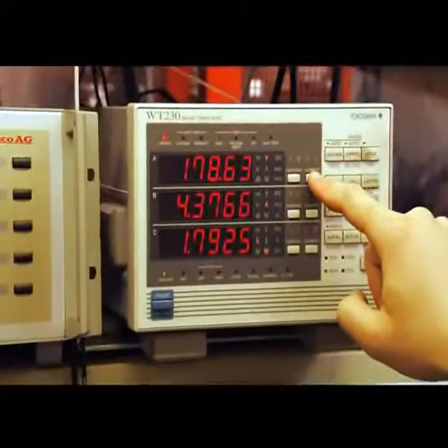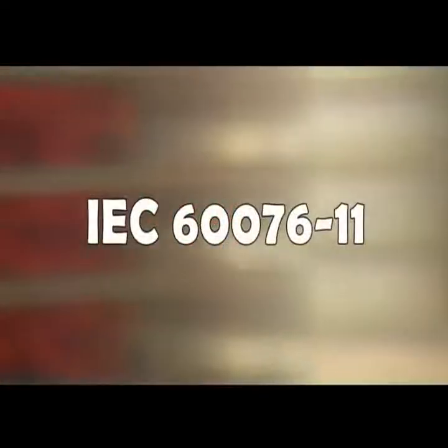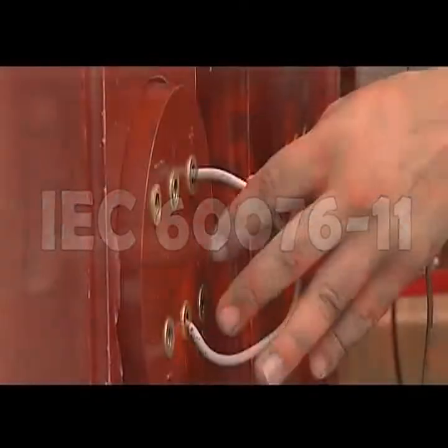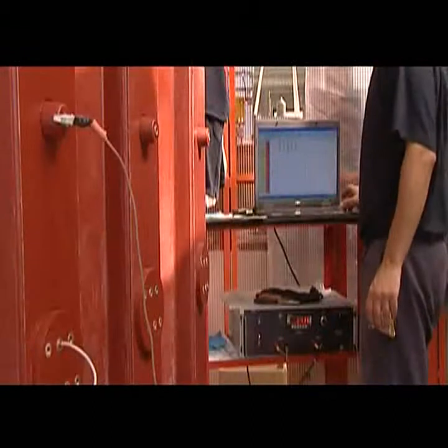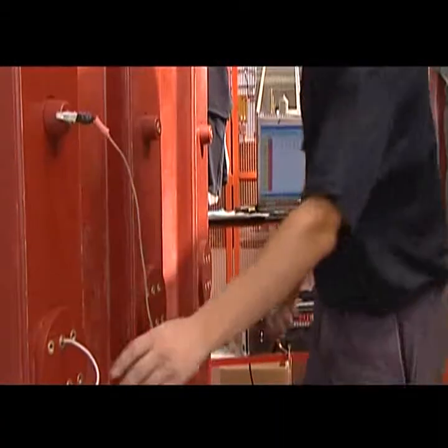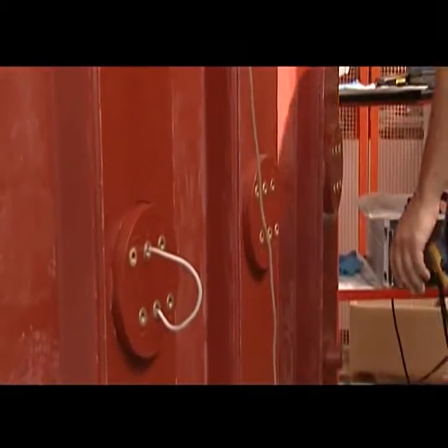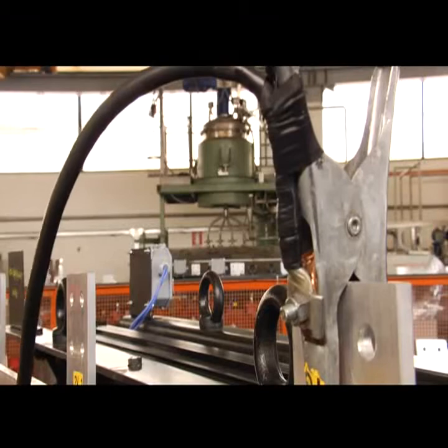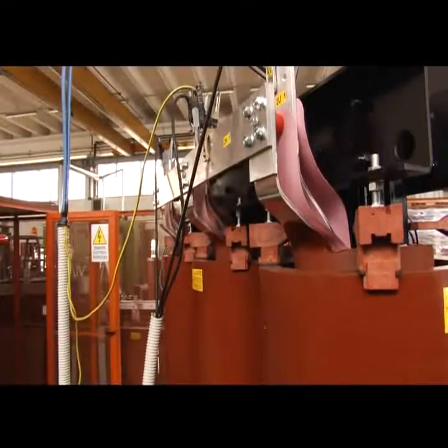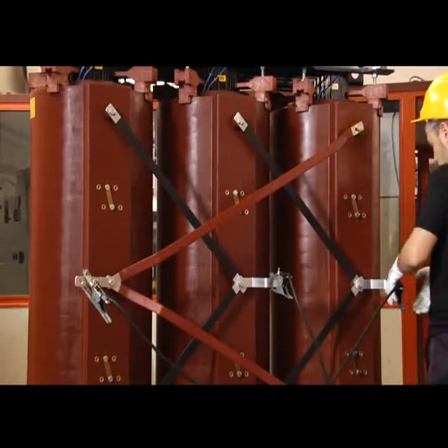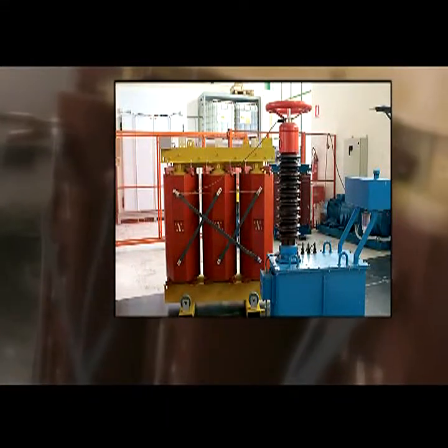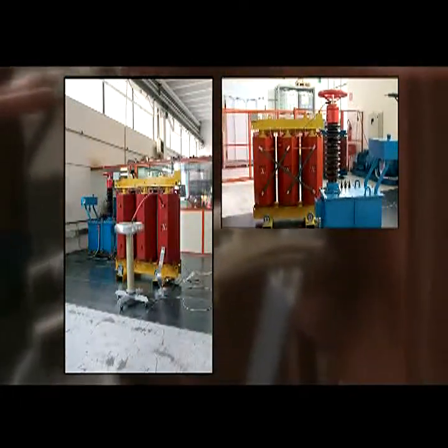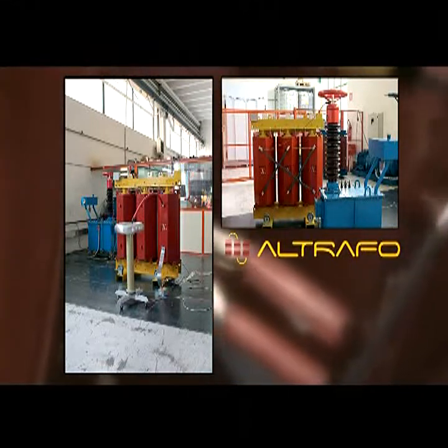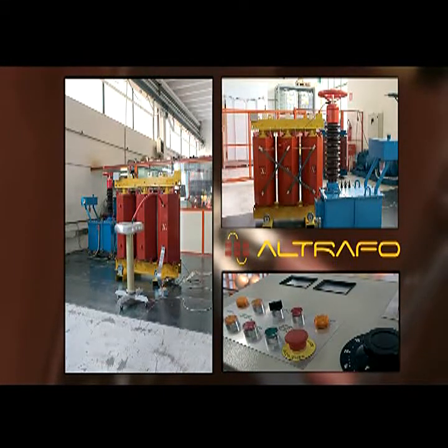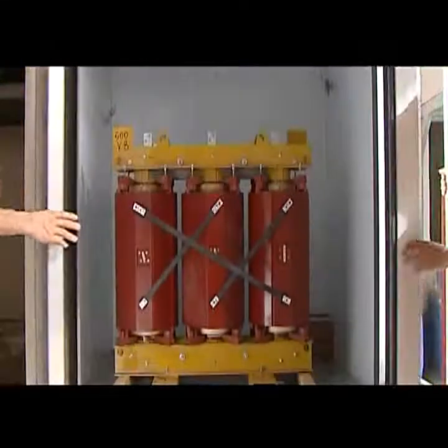In a modern test room, ALTRAFO performs all routine tests according to IEC 60076-11 standard: DC ohmic measure of windings, tappings measure, no-load test, short circuit test, separate source AC withstand voltage test, induced AC withstand voltage test, partial discharges measurements. It is also possible to perform type tests such as the lightning pulse test up to 125 kV. ALTRAFO has a climatic cell where it is possible to simulate climatic and environmental conditions as per C2, E2 classes.